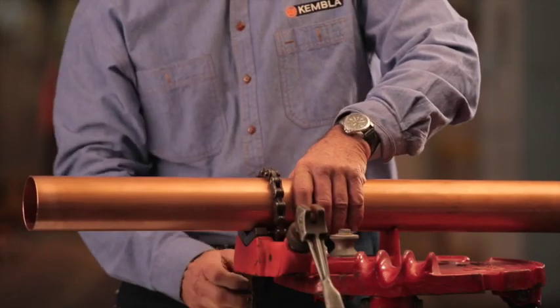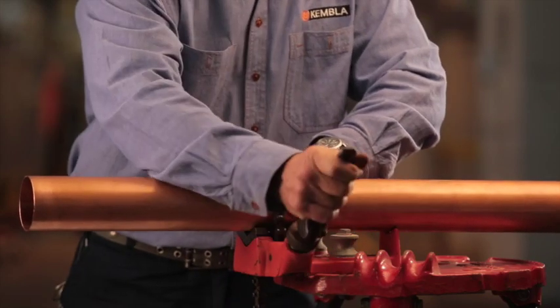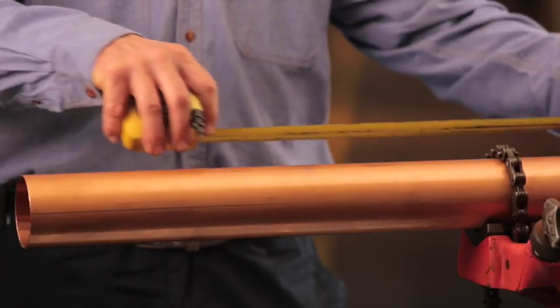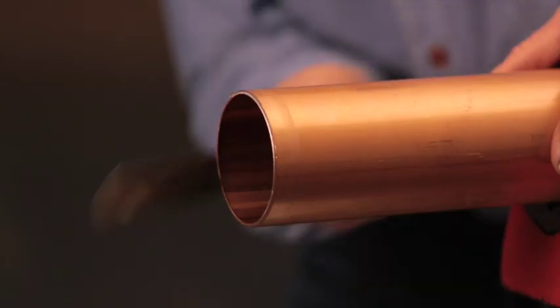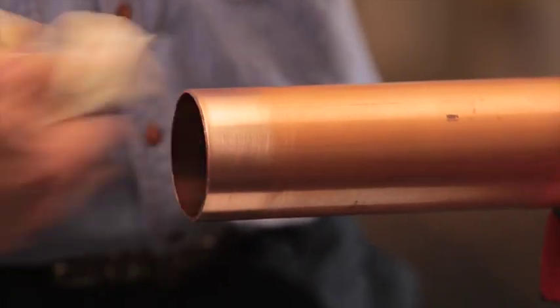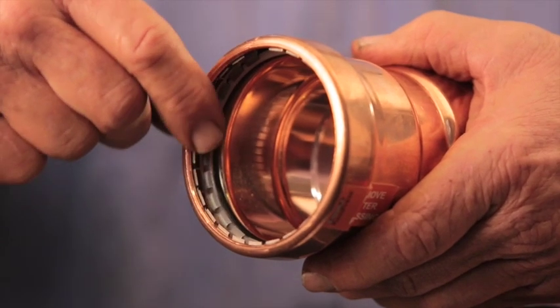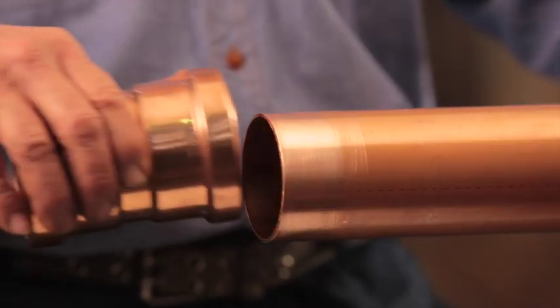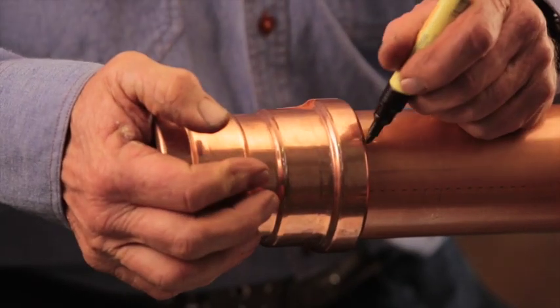For DN 65-100 fittings, secure the tube in a vice or pipe support to prevent any movement. Measure and cut the length of pipe you require using a pipe cutter or a fine tooth saw. Carefully deburr and wipe clean the end of the tube. Ensure you have the correct size fitting and check the stainless steel grip ring, support ring and o-ring are correctly in place. Insert the fitting into the tube until it reaches a complete stop and mark the tube.